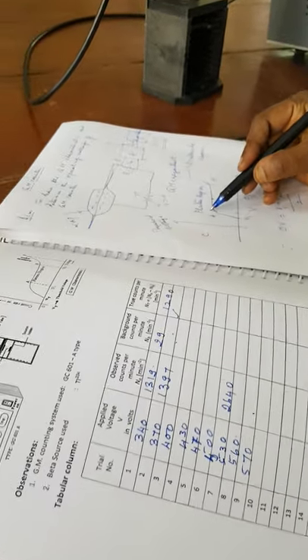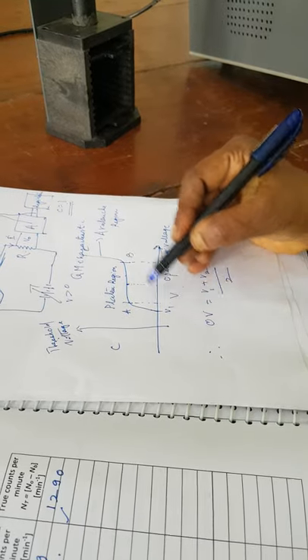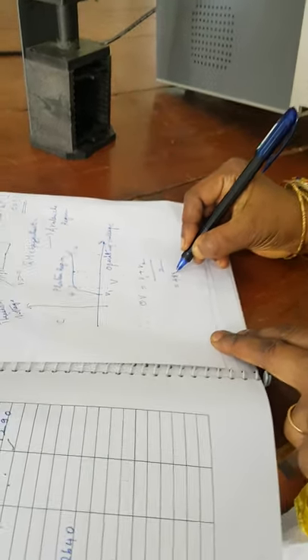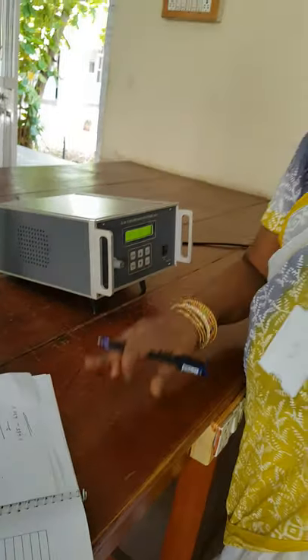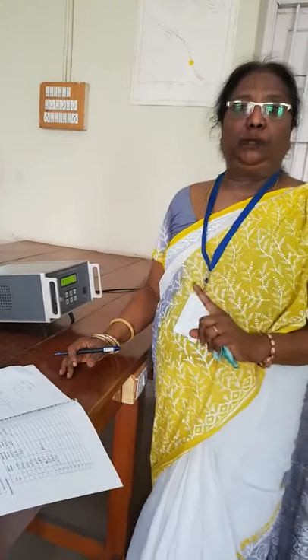Now draw the graph. Where the two counts are remaining constant, that is the plateau region — mark point A and point B, drop perpendiculars, measure V1 and measure V2, then use the formula: Operating Voltage = (V1 + V2) / 2. For this counter you will get somewhere around four hundred. This experiment should be done for every GM counter. Thank you.